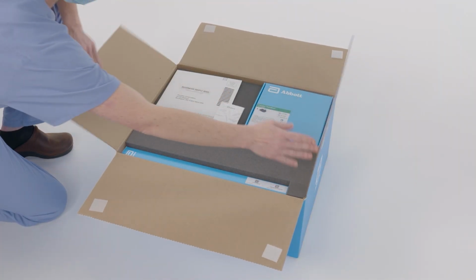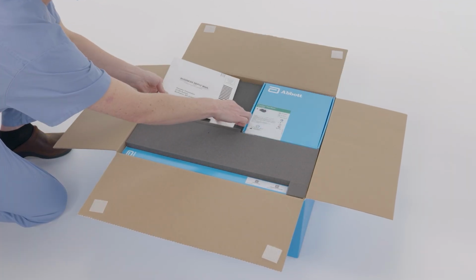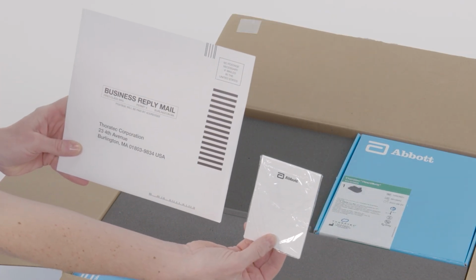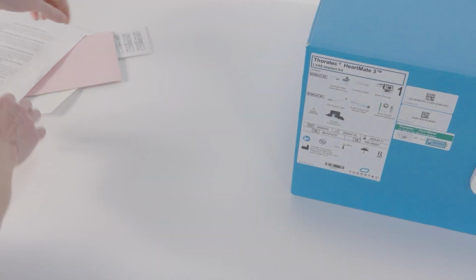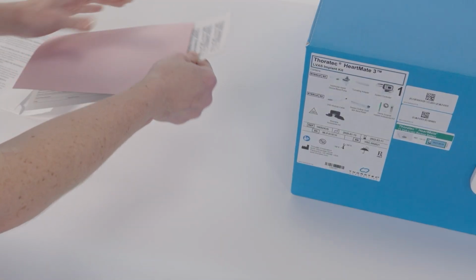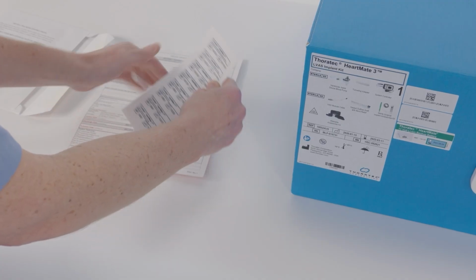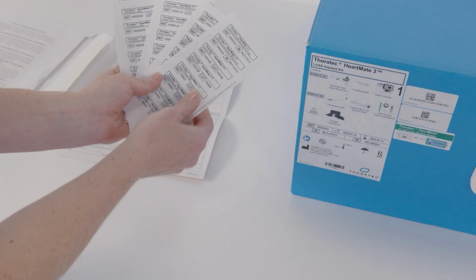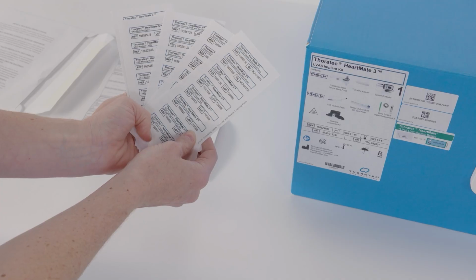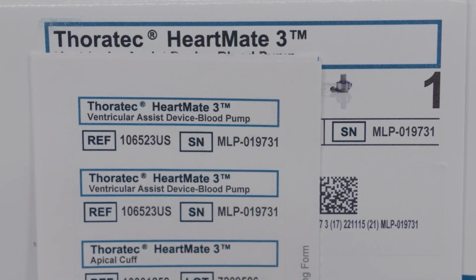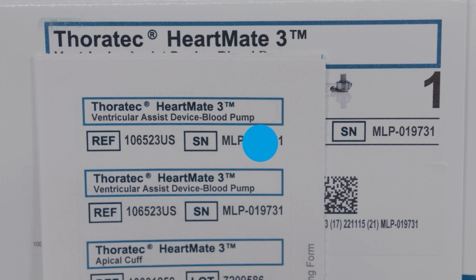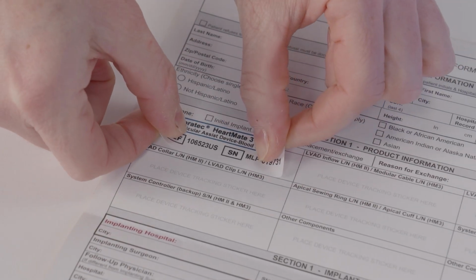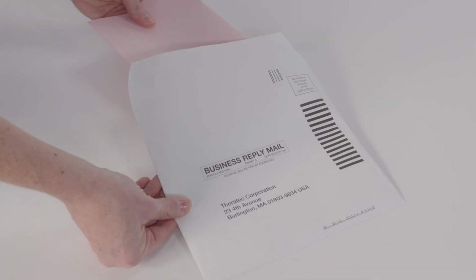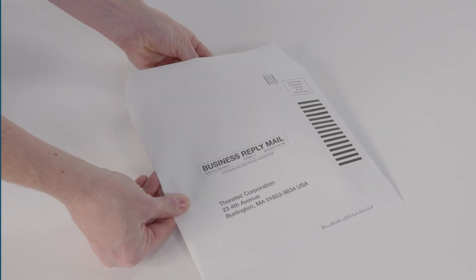After confirming with the surgeon, open the implant kit and remove the device tracking registry form with product tracking labels. The serial numbers of all implanted components and the system controller should be recorded on the device tracking registry form using the stickers included in the envelope. Verify that the serial numbers on the device tracking stickers match the serial numbers on the respective product component boxes. The device registry tracking information must be sent to Abbott, either electronically or as a hard copy.